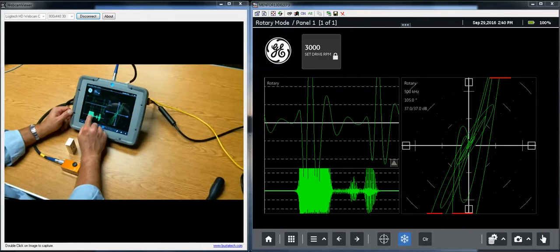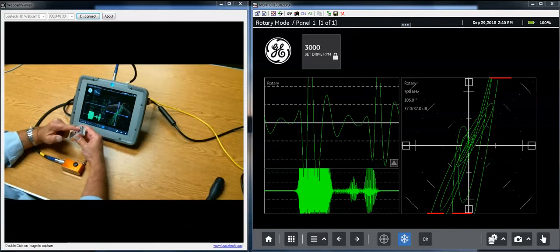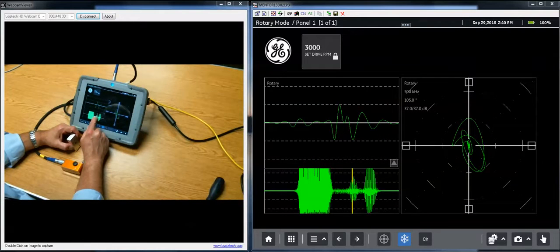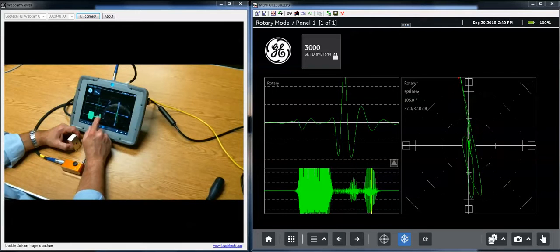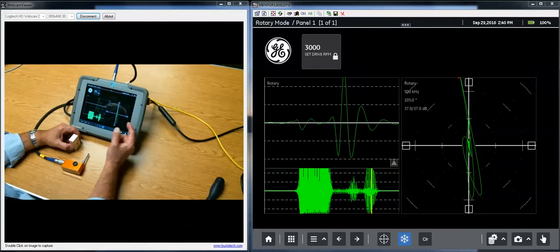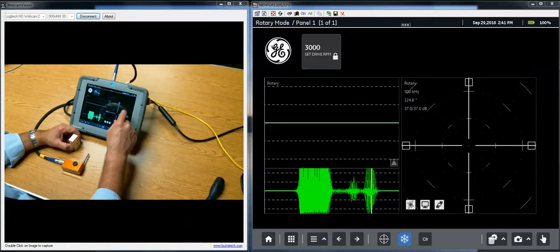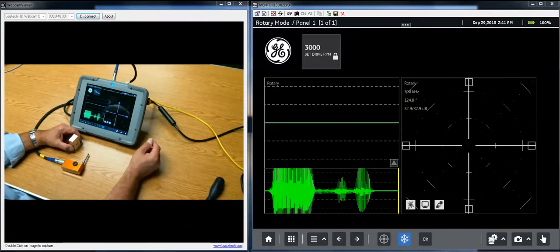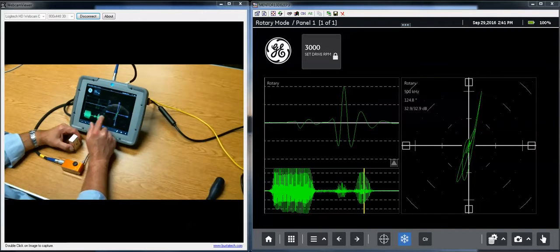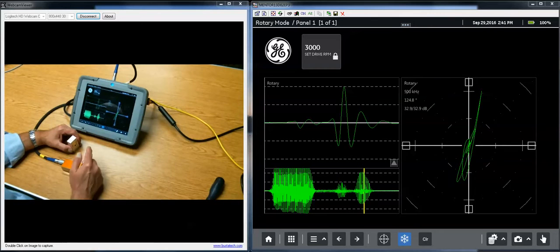So if I put my cursor over here, there's my two cracks in the back half of this standard. If I put my cursor here, there's my side drilled hole. If I put my cursor here, there's my corner notch. And now all of my other gestures that I'm accustomed to, the pinch or the rotate, those all work on these views as well. You notice it recalculated when I changed to phase angle, when I changed to gain, it recalculated the entire buffer in time. Because this is spinning at a high speed, we're using a very high sample rate here.